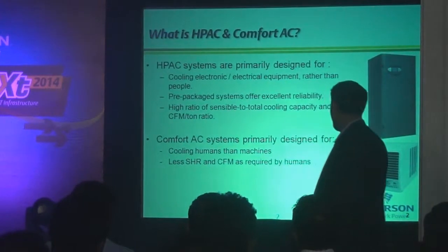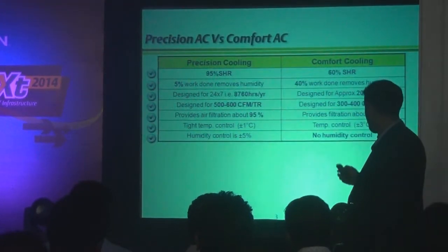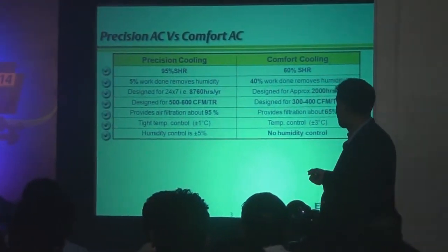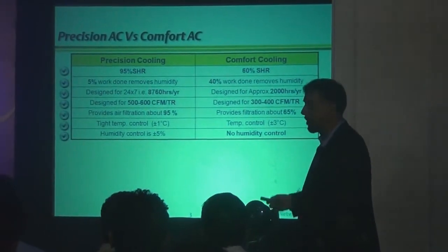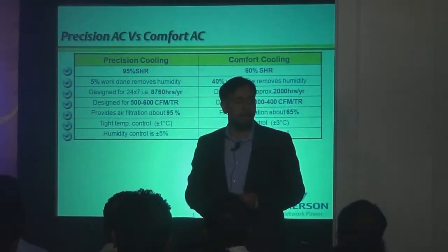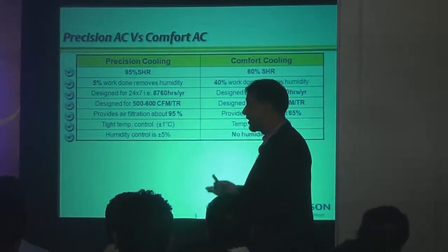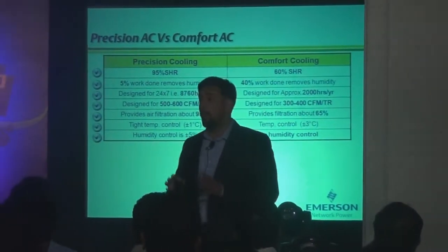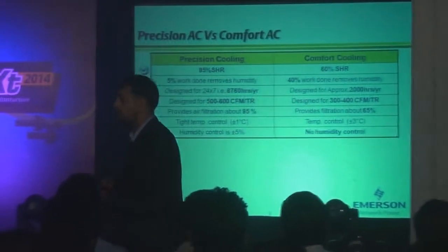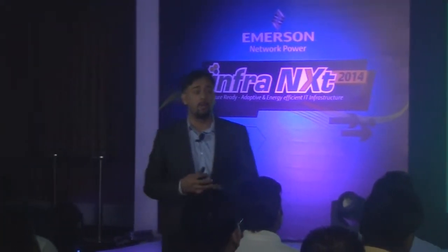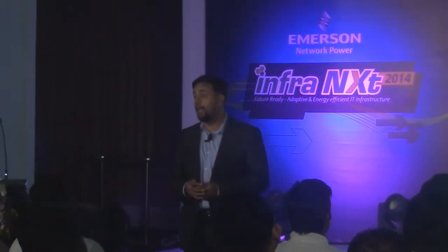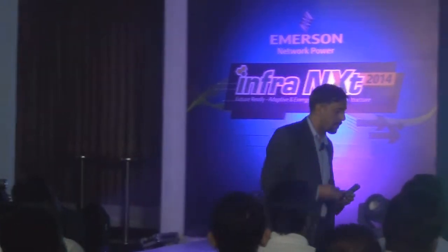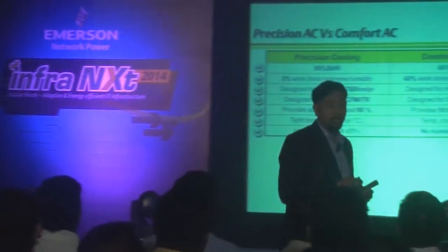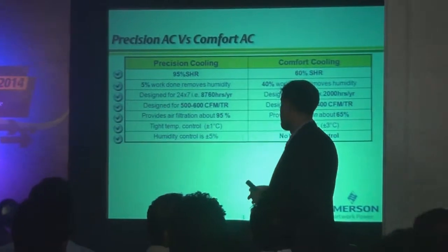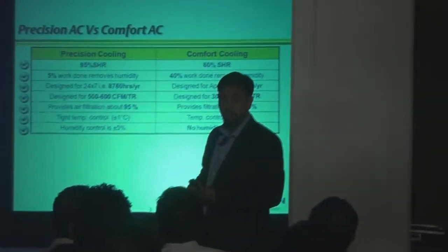That's the basic fundamental difference. We have more than 95% sensible heat ratio requirement for such cooling applications, but for comfort it's about 60 to 70%. Filtration is also important—data center and server room applications require good filtration, up to 95% down to 5 microns, since we don't want dust or small particles accumulating on electronic equipment or PCBs, so it needs to be filtered to a good level.